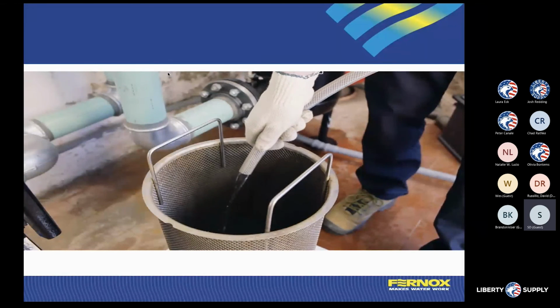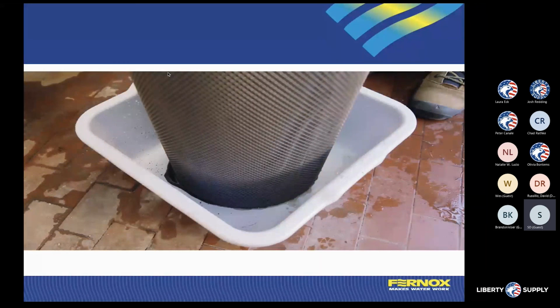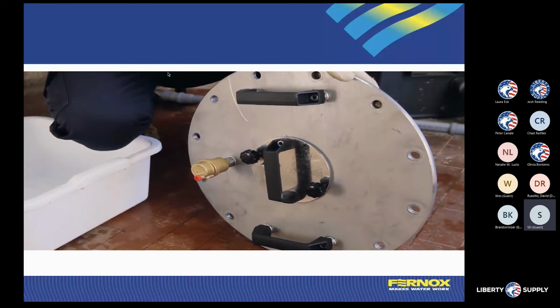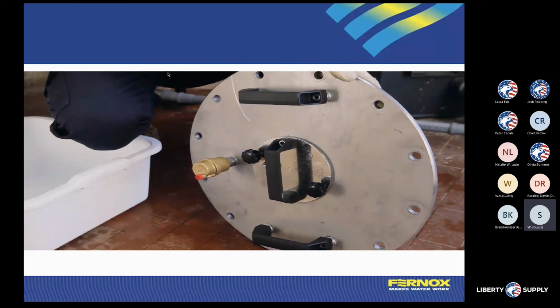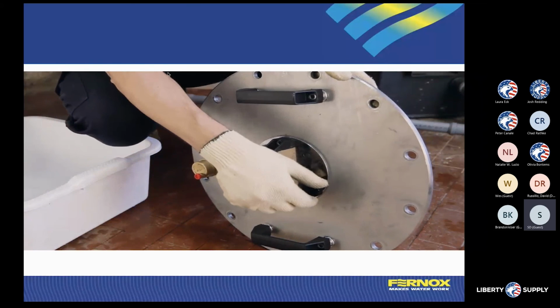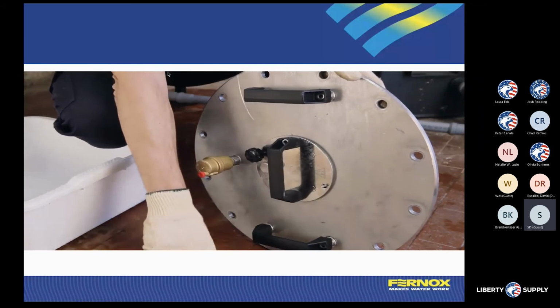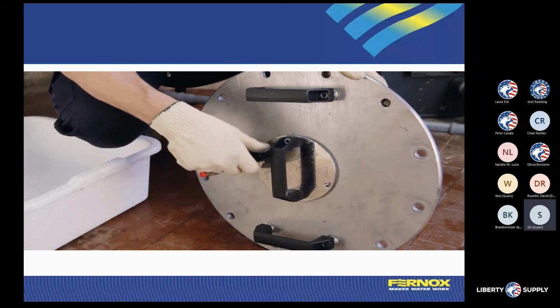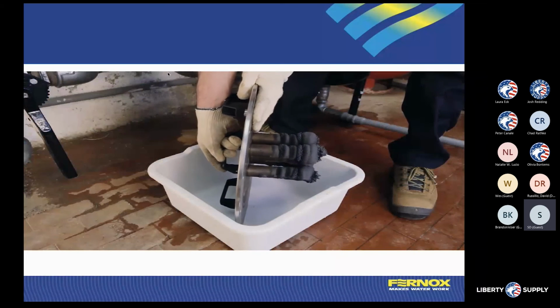We also have a 2-inch to 1/2 inch, which we call our X-Mag filter, that you also can add a sediment filter, a micron bag style filter that will go inside of this. So you can not only get the sediment down to a fine level, especially if you have a really dirty system, you're also going to add the bag filter, or you can do an external bag or water style filter for sediment as well.